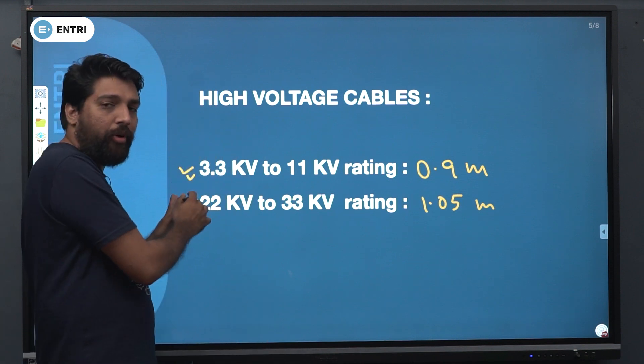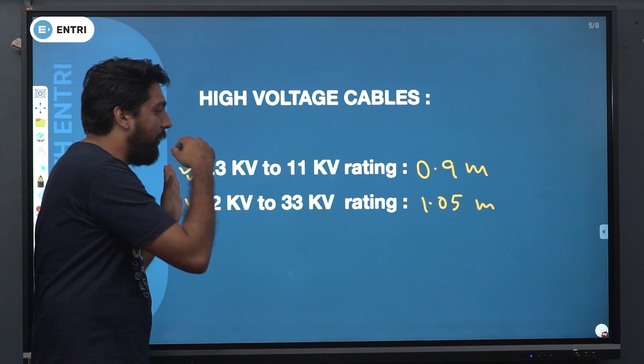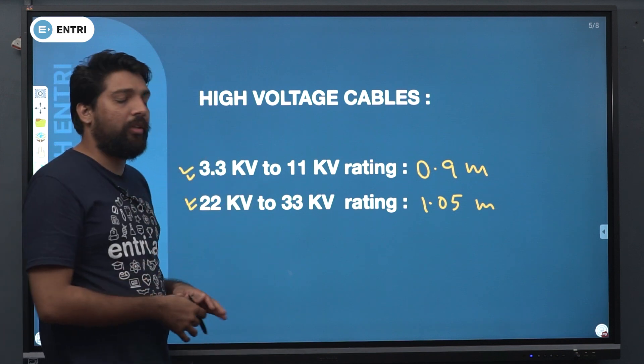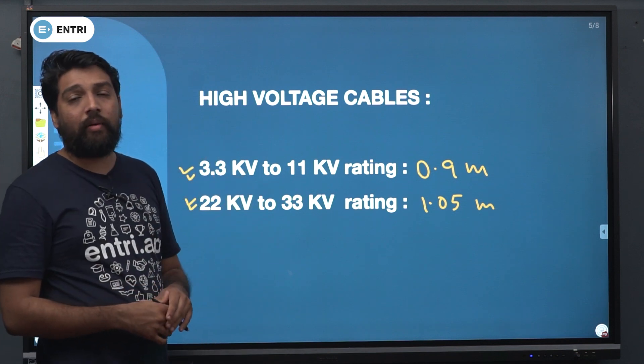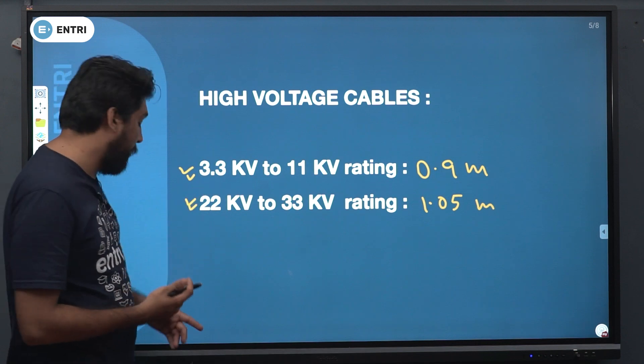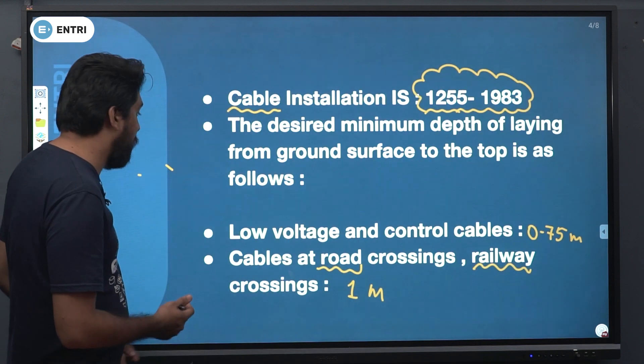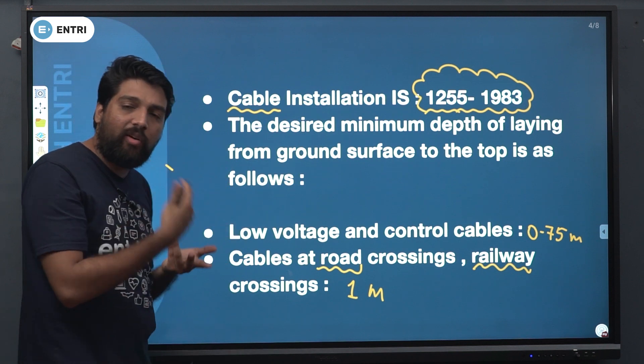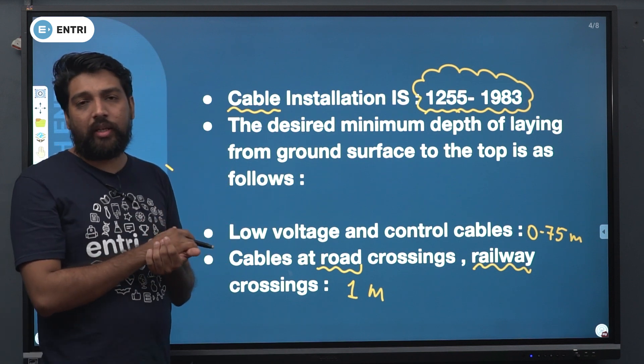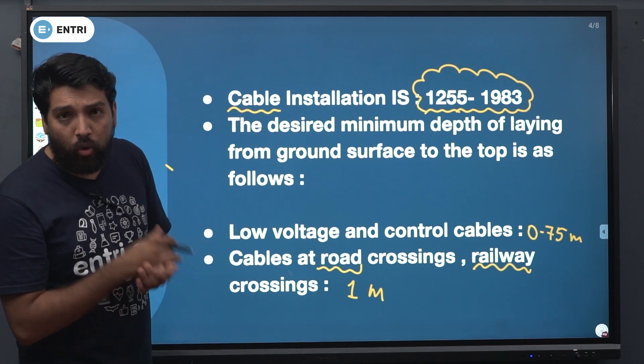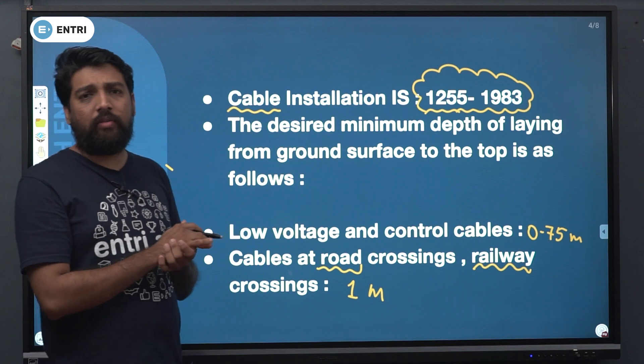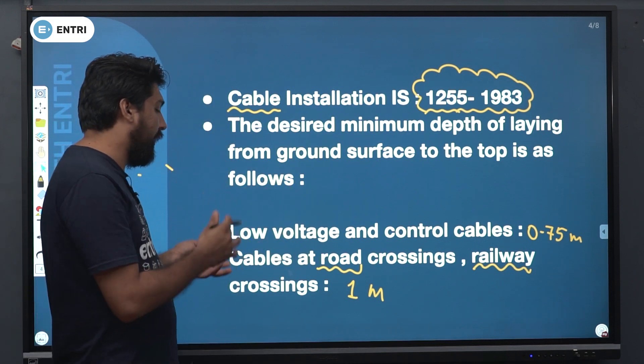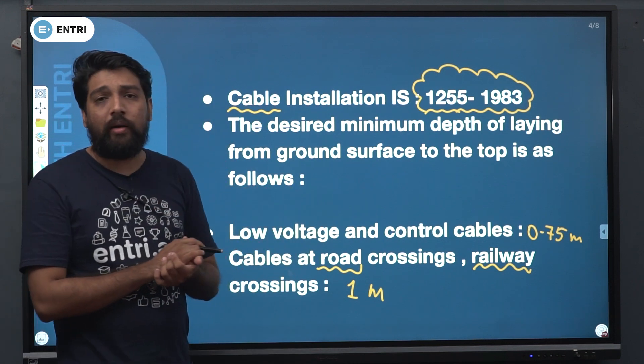In high voltage cables, 3.3 kV to 11 kV: 0.9 meters. In 22 kV to 33 kV: 1.05 meters. So the question is: low voltage cables and low voltage control cables are 0.75 meter. If you use road crossings, river crossings, or railway crossings, it is 1 meter.